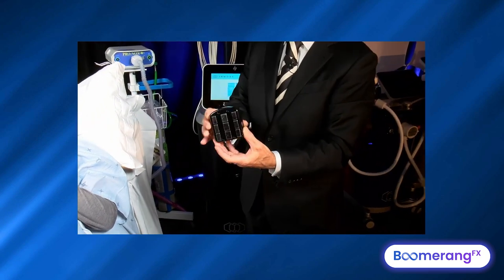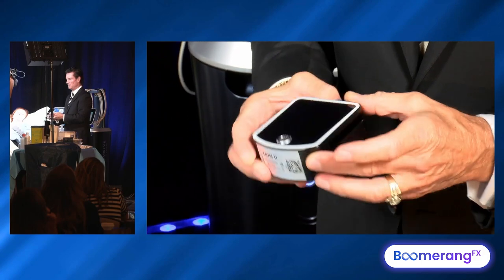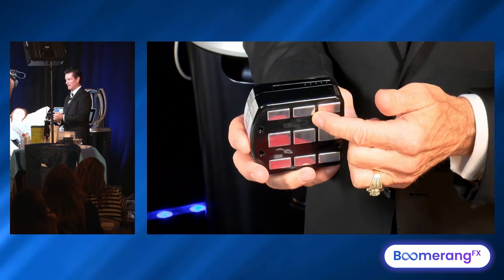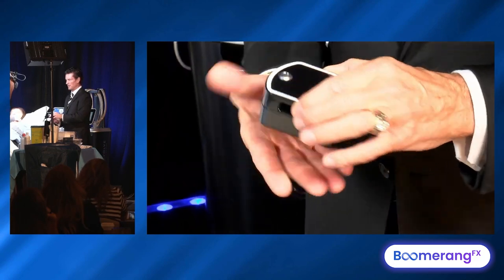If we look at what it looks like, this is the undersurface, this is the top, there's a little place where you plug your cord in that goes back to the software in the CPU. It's fairly thick because it has all the sensors we need in there, which is contact, temperature cutoff, impedance, rate of rise of temperature, and then it's got a little belt fixation system to allow you to put that on.